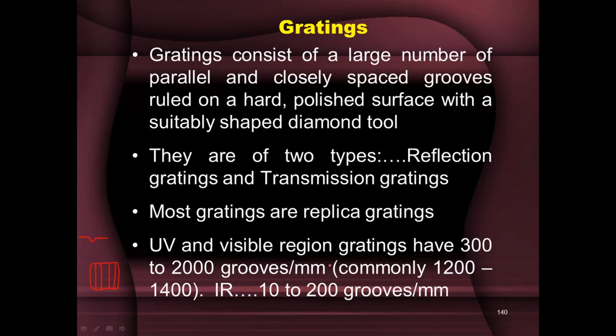UV and visible region gratings have 300 to 2,000 grooves per millimeter, and commonly around 1,200 to 1,400 grooves per millimeter. A millimeter is the smallest division on your scale — within that, you have to draw 1,200 lines accurately, all to the same depth, the same angle, the same spacing, and all parallel to one another. That's why making master gratings is quite difficult, requiring very sophisticated technology and hence being expensive. That's why replica gratings, created from original gratings, are generally used in instruments.